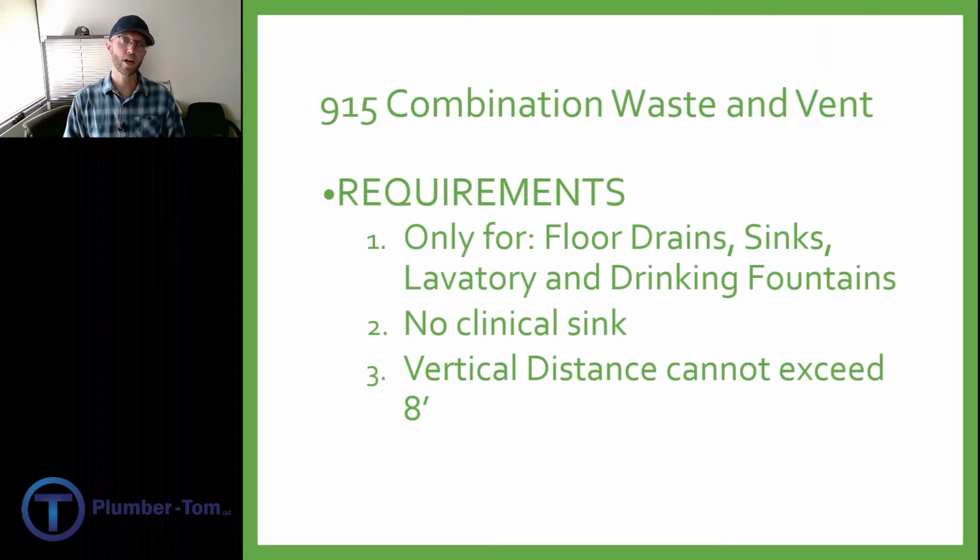The requirements for a combination waste and vent system include limitations, meaning you can't use this for any and every fixture. It's only for floor drains, sinks, lavatories, and drinking fountains. No clinical sinks. That's like a big square mouth toilet for bedpan washing. That doesn't count. Now it also is limited to a vertical rise of 8 feet.